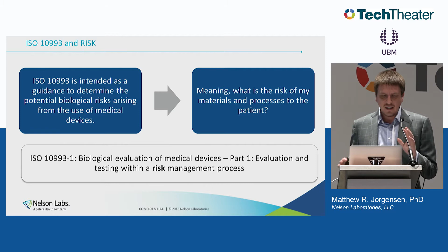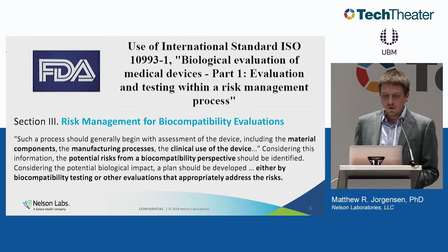You can see in the FDA's document, they spell it out explicitly that as you evaluate biocompatibility, you should be thinking about the material components, manufacturing processes, and previous clinical use, and you evaluate potential risks from a biocompatibility perspective, and then you evaluate those either using testing or other evaluations that appropriately identify the risk. And the feeling that we've had from our European regulators especially, and now it's moving more and more into the FDA, is that they really expect you to evaluate as a first option as opposed to doing any animal tests. So if you are going to do an animal test, you should be able to justify why you had to do the animal test rather than just defaulting to it in the first place. So this is really a different direction.